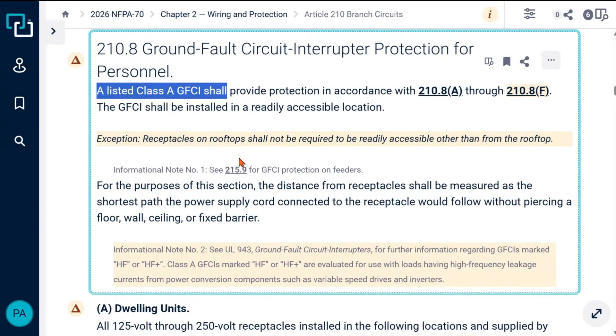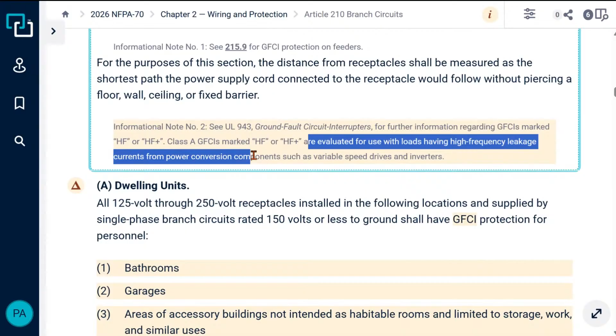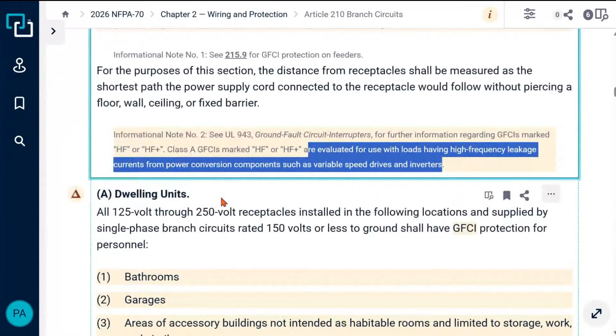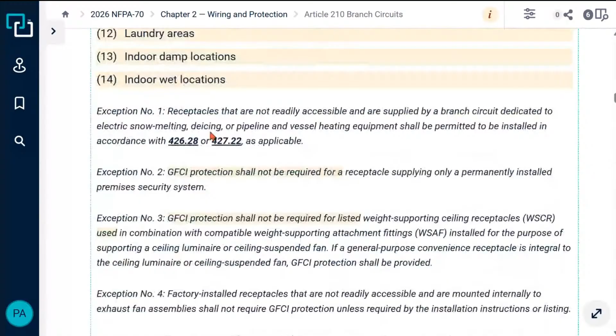But you see down here, we do have an informational note just reminding us that UL 943, it says for further information, markings HF or HF plus. It says Class A GFCIs marked HF or HF plus are evaluated for use with loads having high frequency leakage currents from power conversion equipment, such as variable speed drives and inverters. It's still just a general rule.